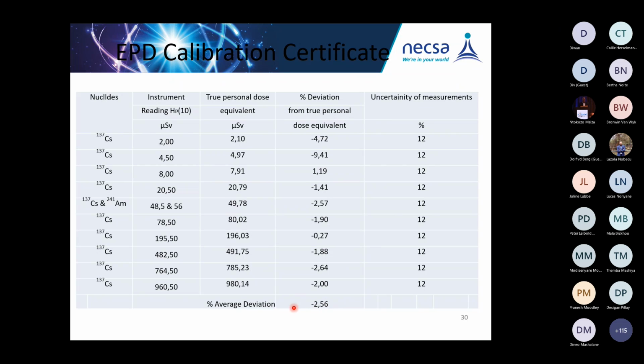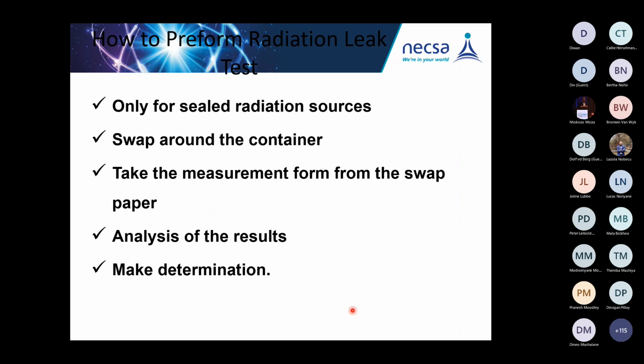If you look at our guidelines, TR18, the average percentage deviation should not exceed plus or minus 15. And the single percentage deviation, that is the intrinsic error, is there in your certificate at the bottom of each table. From all the laboratories, you will see that. This is the intrinsic error. This point, for a single point of measurement, should not exceed plus or minus 25. And those are the keys that we use in the determination of pass or fail.